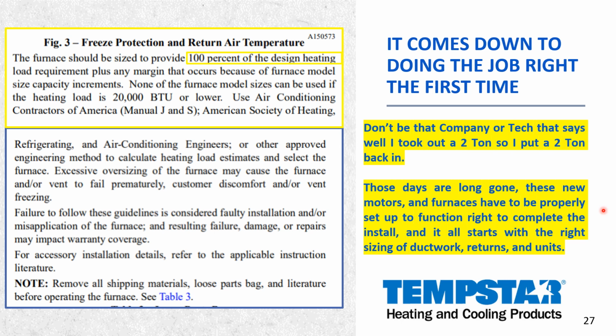When it comes down to doing the job right the first time, don't be that company or tech that says, well, I took a 2-ton out, so I'm going to put a 2-ton back in, because you haven't checked the ductwork or you haven't checked the supply. And when you're setting this system up, you need to know what your CFM is. What do I got to have? Why did I put a 2-ton in? Well, I put a 2-ton in because I need 800 CFM.